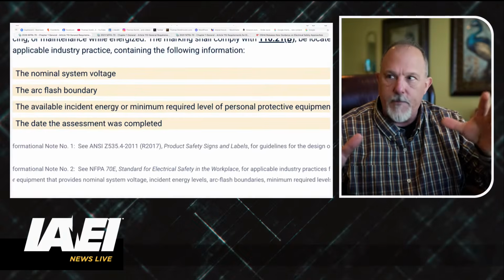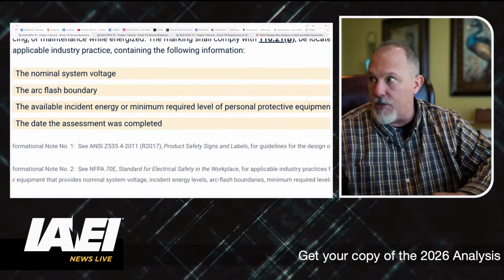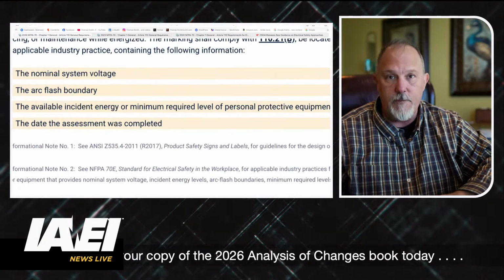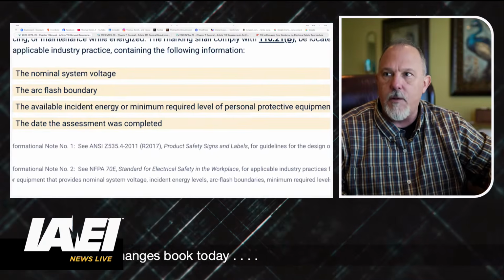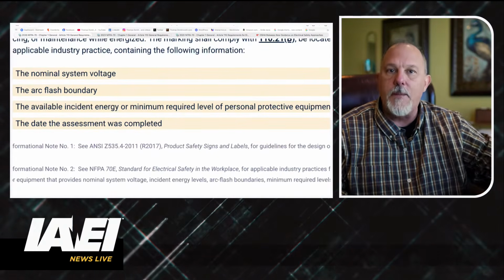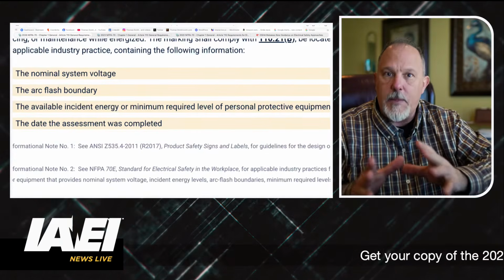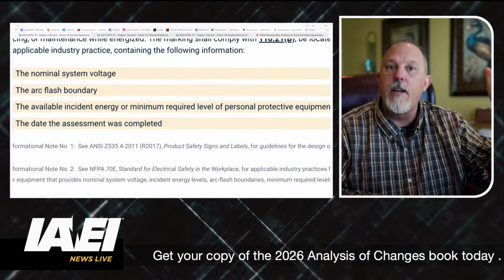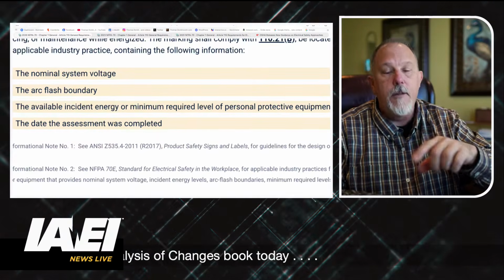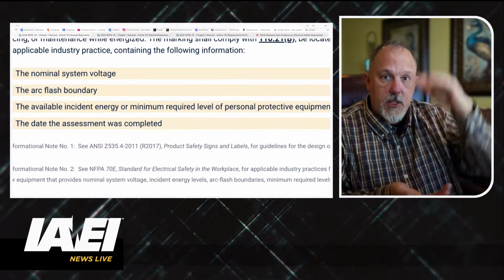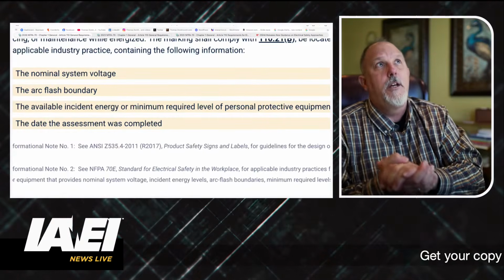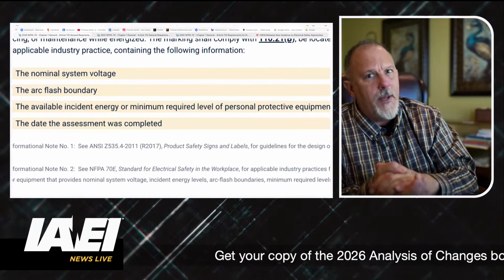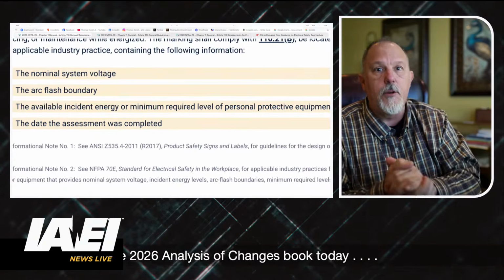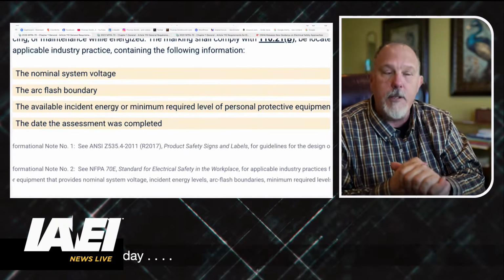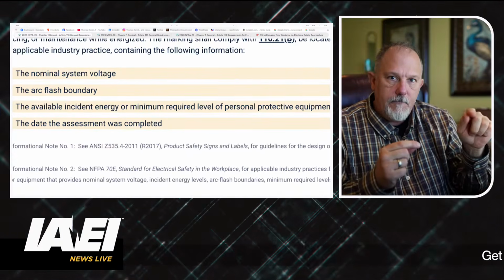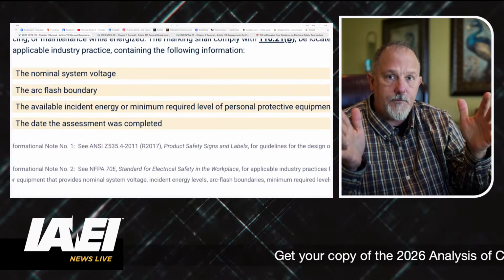So if you're looking at a piece of equipment, you can calculate the incident energy and use it. That's what you have there, the available incident energy. And then the minimum required level of personal protective equipment would be your PPE category method. If you think about the PPE category method, when you go to Article 130 of 70E, there's a nice table in there that says what the equipment is. The first line is a panel board, I believe a 240 volt panel board. The second line is a panel board above 240, say a 480 volt panel board. And you have to meet the criteria inside that table.